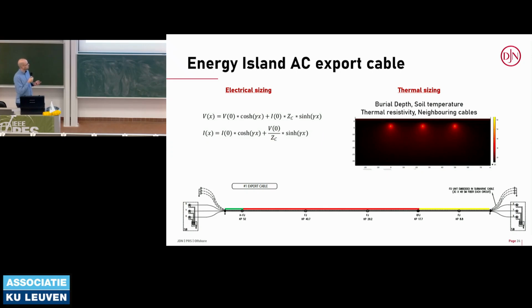So we handle this through thermal sizing, but that's not the only issue. As Thierry already mentioned, if you put 3 cables next to each other you get a thermal impact that isn't described in any standard, or not described enough. It depends on whether you run a finite element model like we've done here. You can see that spacing them 25 meters apart is actually already okay, but these things need to be calculated since they're not in line with current standards.